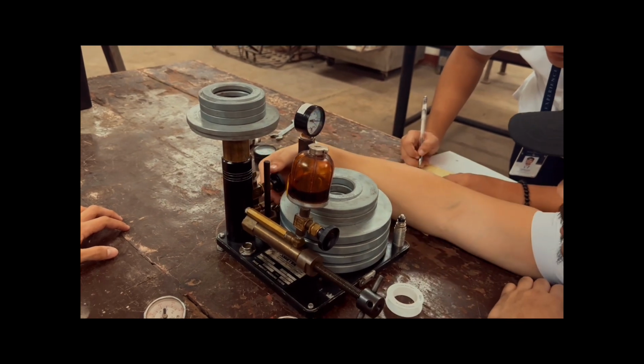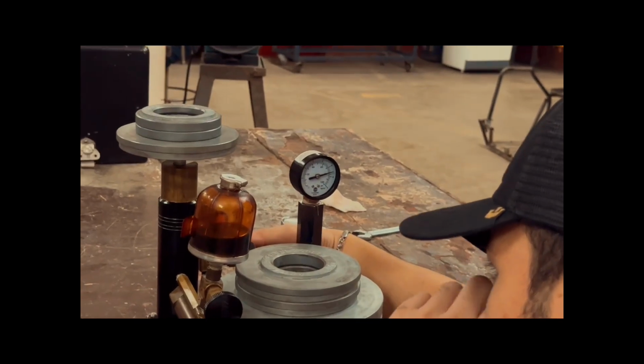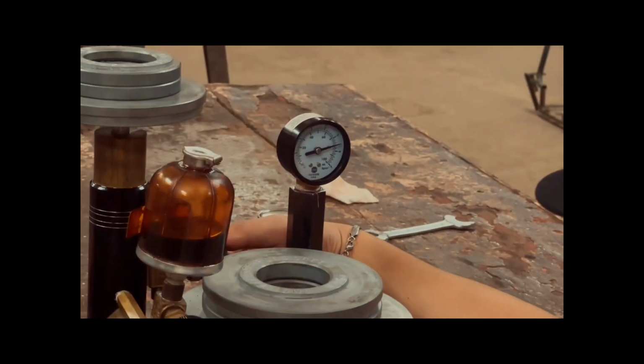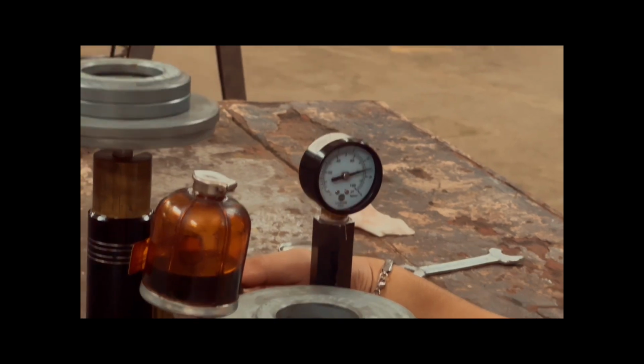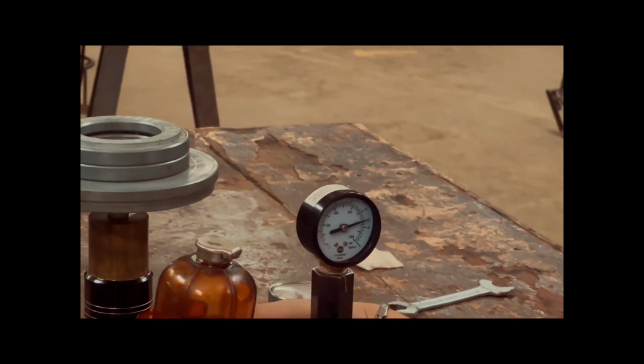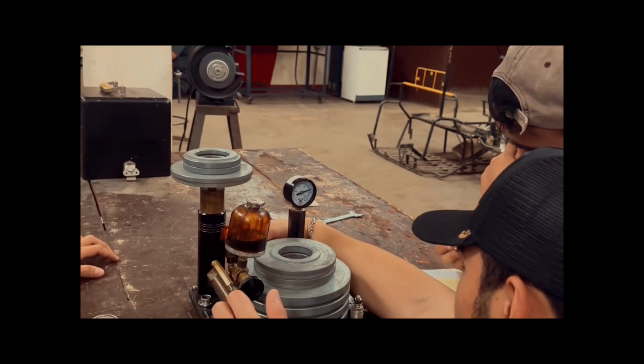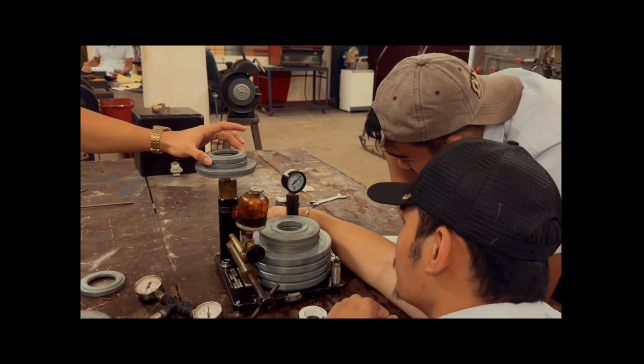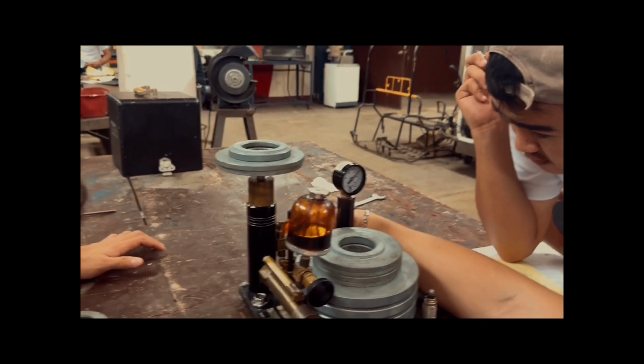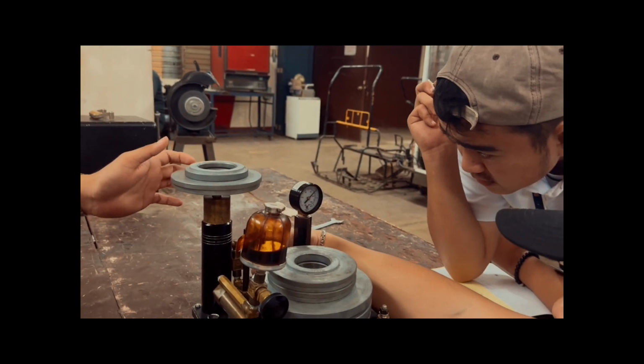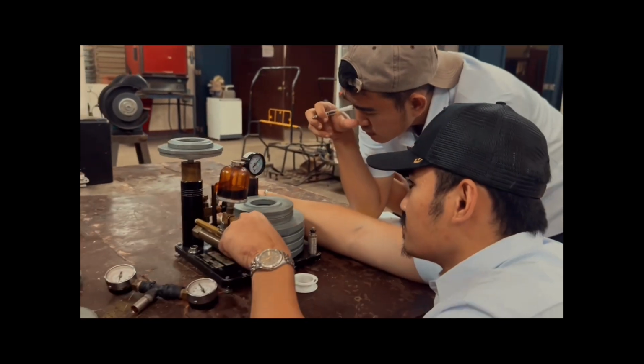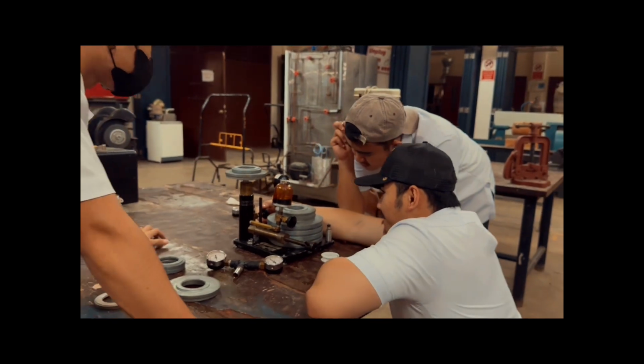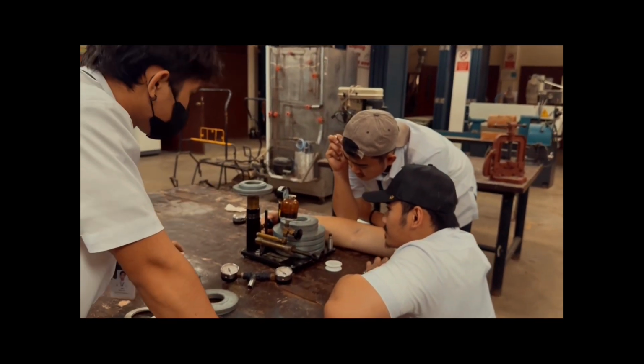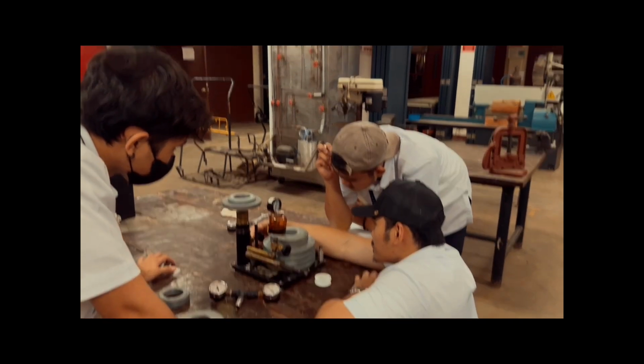We started at 4 pounds which shows the same pressure of 89 psi. Then went to 3.5 pounds that shows 79 psi. Then went to 3 pounds that shows 68 psi. Then unloaded to 2.5 pounds that shows 58 psi. Then went to 2 pounds that shows 51 psi. To 1.5 pounds that shows 47 psi, and to 1 pound that shows 26 psi, and lastly went to 0.5 pounds that shows 13 psi.